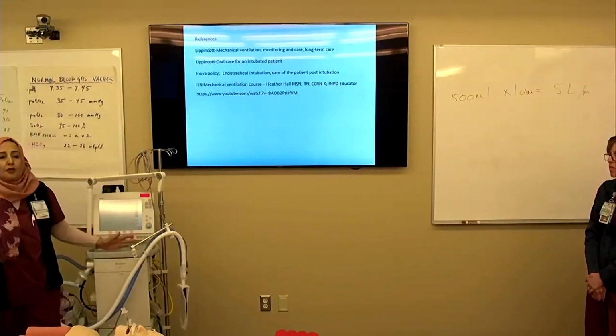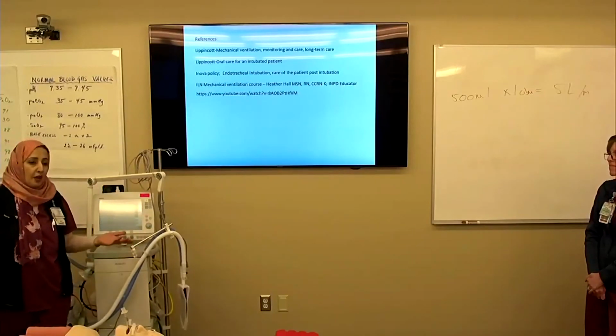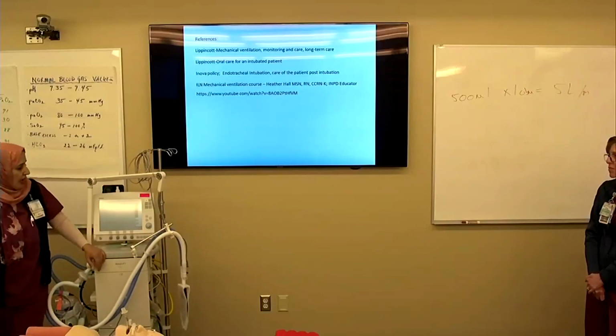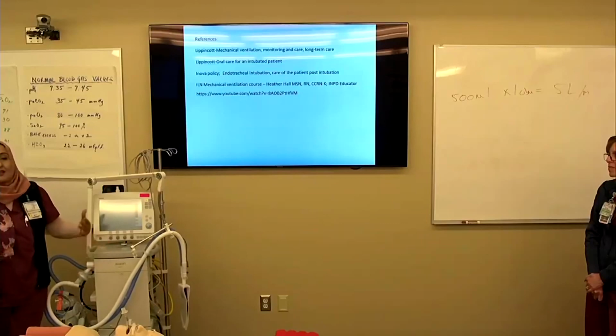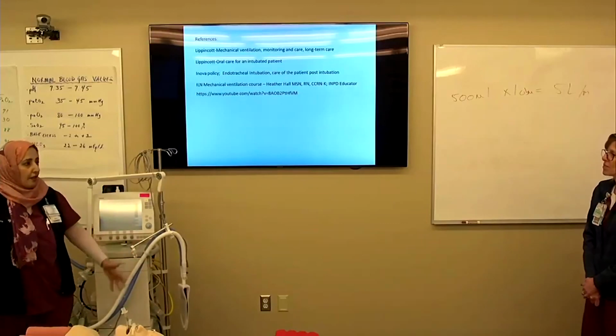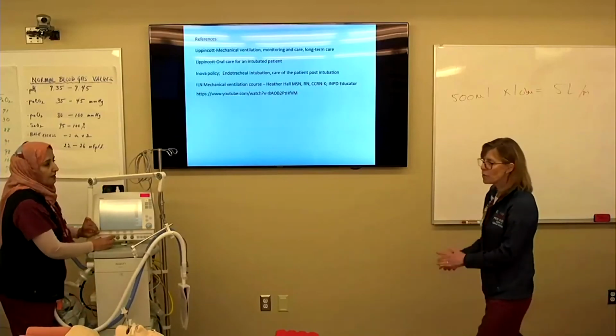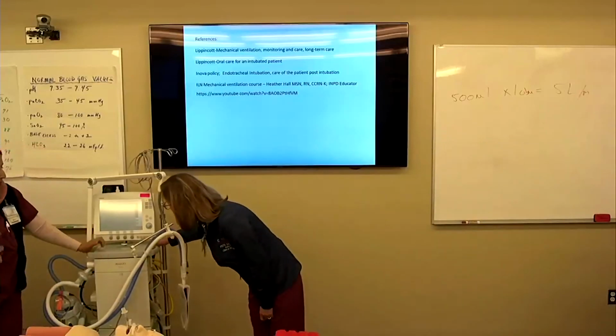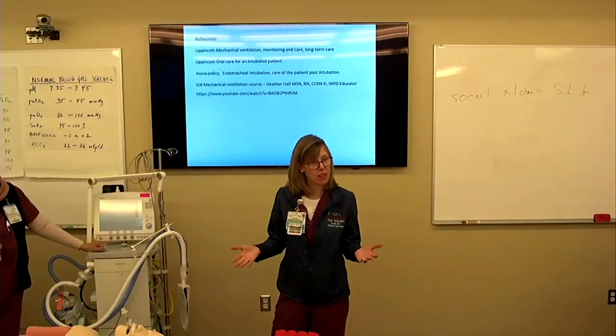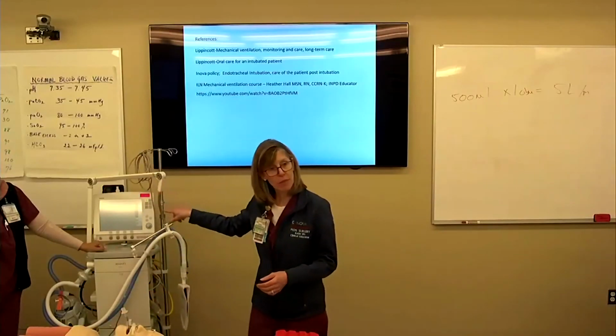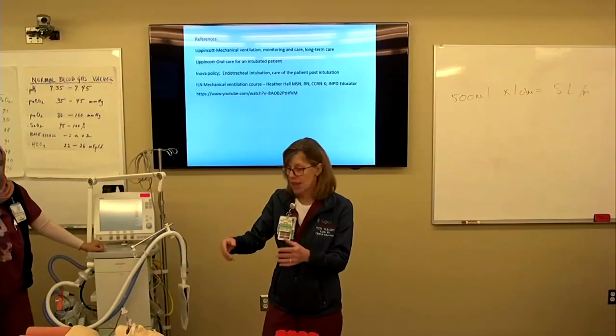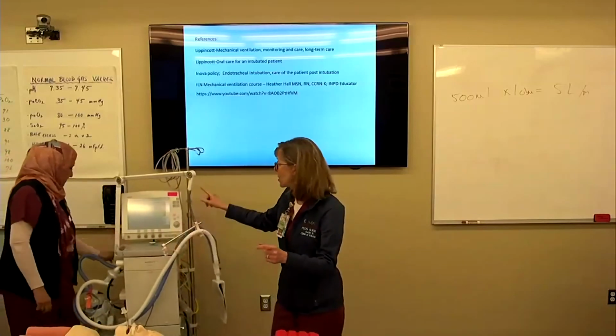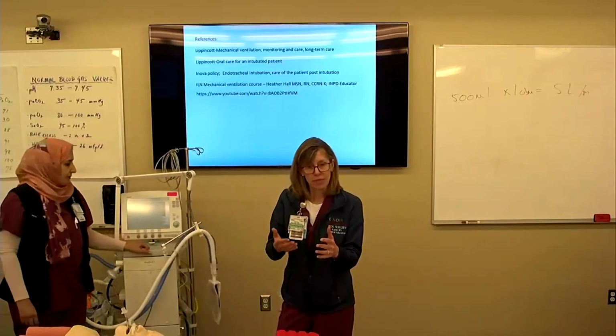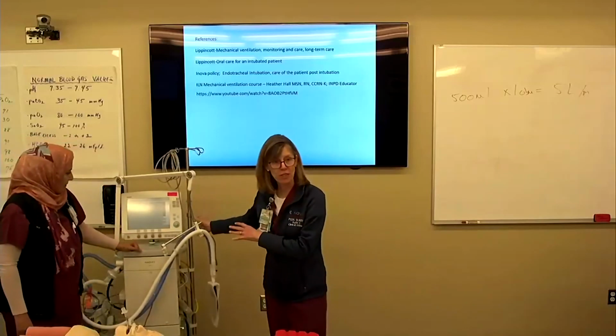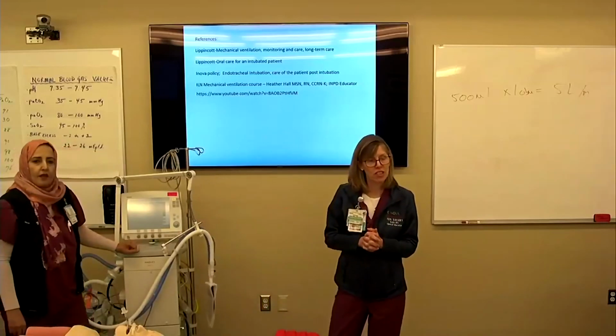Of the different modes, the most important and common mode that we use here is PRVC, pressure regulated volume control, and we use it for all the patients, because the vent is very smart, sensing the pressure and giving the patient a precise tidal volume. May I add one very important thing: as you said, the one button that we can press is our O2 breaths, where we provide a minute of 100% O2 prior to suctioning our patient. We press that button, it gives the patient 100% oxygen for just a minute, then we can inline suction the patient, and when we're done, we press that button again to give the patient another minute of 100% O2, and then it automatically goes back to its previous setting. So just remember, we always want to pre-oxygenate before we suction.